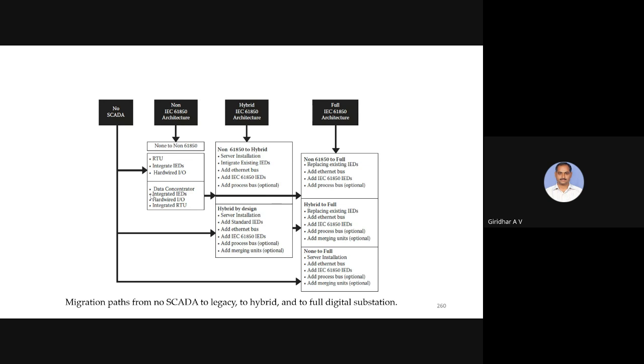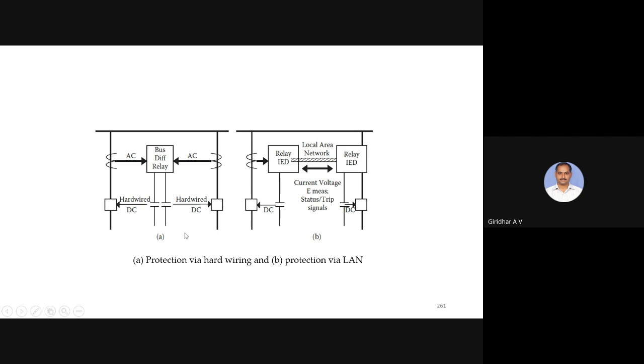If you look at hybrid IEC 61850, you can see how they are using fully digital substation architectures. They are using the IEC 61850 process bus and replacing existing IEDs. In the hybrid, they are adding IEC IEDs, using an Ethernet bus and process bus. The different typical protection hardware, how they are used for control, local area networks via LAN. Nowadays they are implementing these aspects.